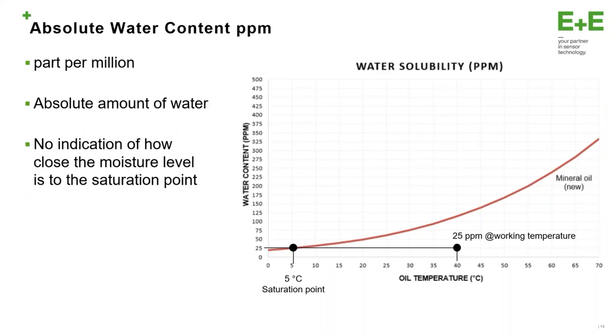How can we quantify the water? We can quantify it in the absolute way, just measuring the absolute water content, typically expressed in PPM (parts per million). It's a number which describes the amount of water, but it's very simple and we have no indication of how the moisture level relates to the saturation point. For example, if we have 25 PPM at the working temperature, we just know that we have 25 PPM inside our transformer. Checking with the water solubility curve, we see that if we cool down this 25 PPM down to 5 degrees Celsius, we have condensation — but we don't know how far we are with respect to the saturation point.